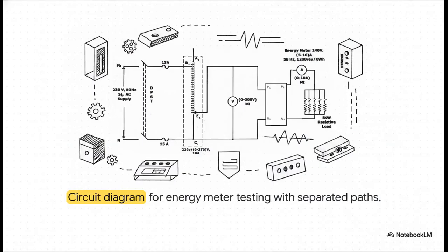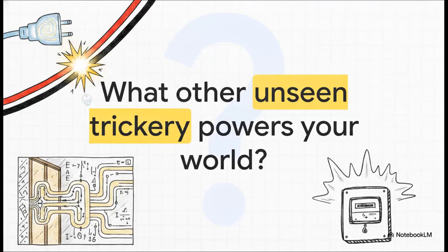When you actually map all of this out in a real lab calibration circuit, you can see how all these distinct modular pieces, the transformers, the voltmeters, the ammeters, and the separate power paths, they all fit together like a giant puzzle. And this intricate, highly controlled testing environment is absolutely only possible because those internal watt-meter coils are intentionally disconnected by default. From using clever illusions like phantom loading to save energy, all the way to intentionally short-circuiting live wires just to avoid getting hit by a lethal 76 kilovolt shock, it really does change how you look at the grid, doesn't it? It kind of makes you wonder, what other invisible engineering secrets and high-stakes mathematical puzzles are silently humming right behind the walls of your own home?